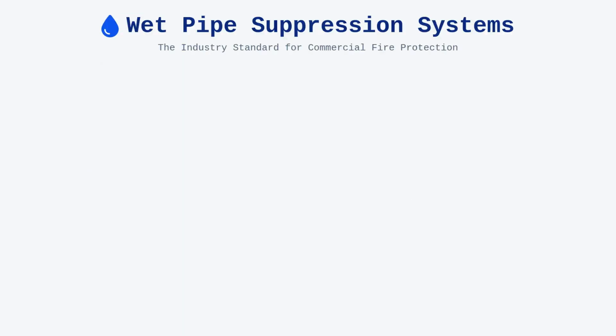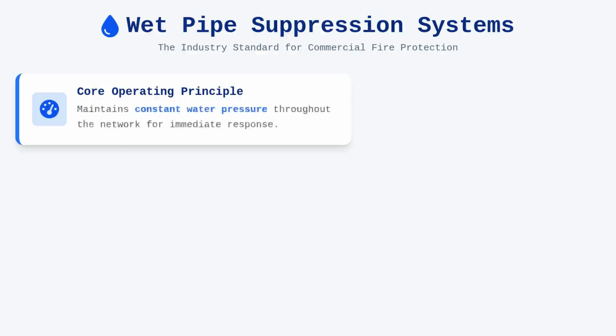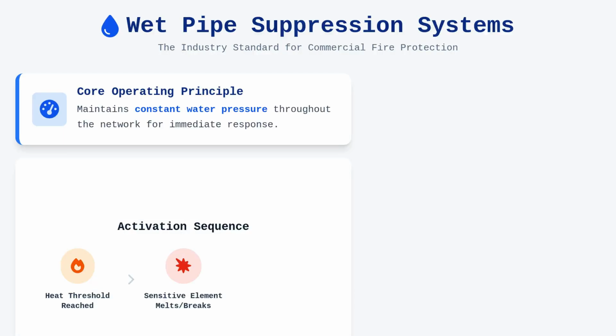Wet pipe systems represent the most common and reliable form of automatic fire suppression in commercial environments. At the core of their design is the principle of constant water pressure within the piping network, held back by a thermally sensitive sprinkler head. When the temperature at a specific head reaches its activation threshold, the heat-sensitive element breaks or melts, allowing water to discharge directly onto the ignition source.